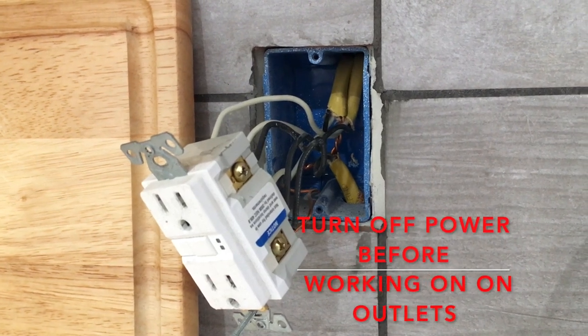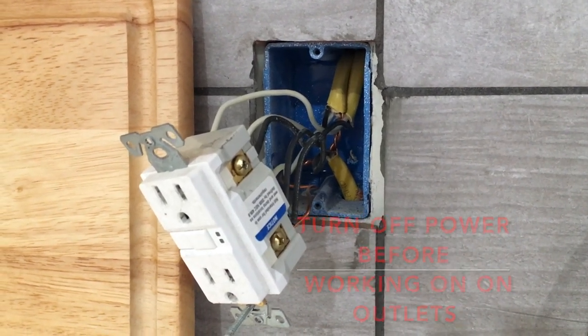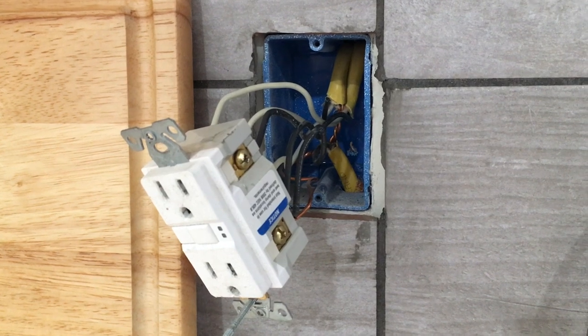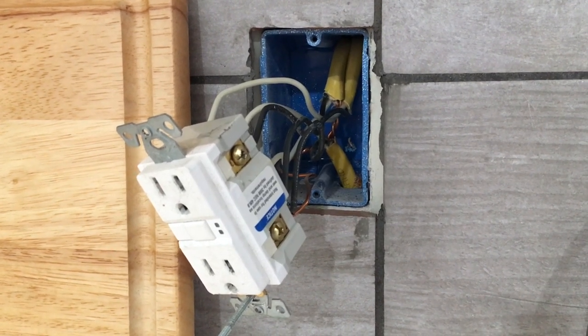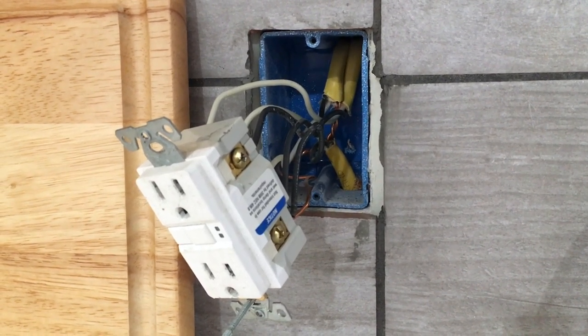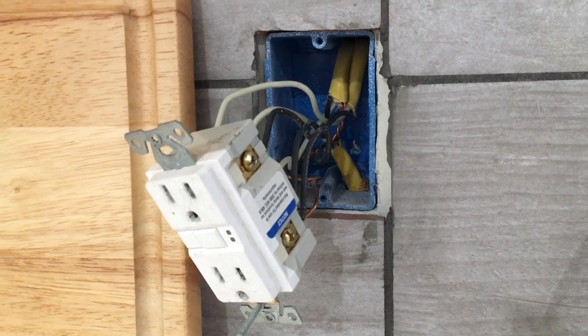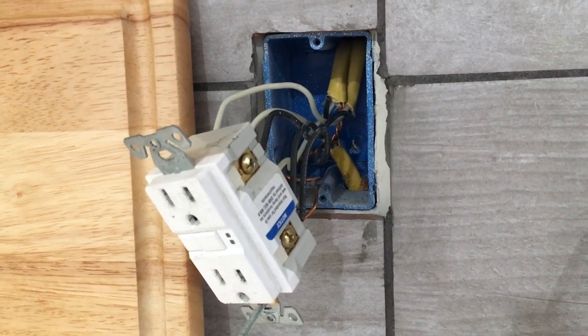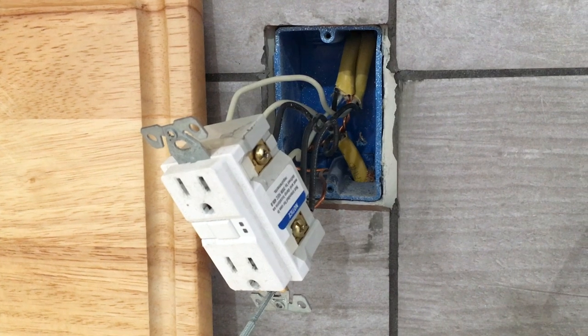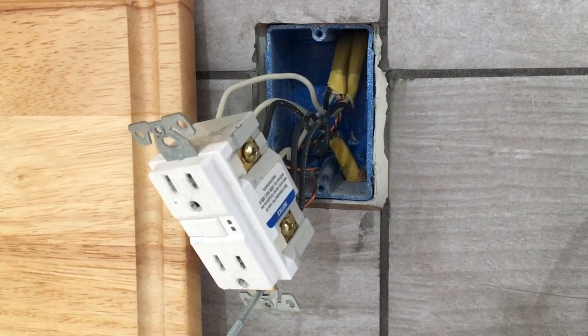This is a troubleshooting example. Here we replace a defective GFCI outlet that keeps tripping intermittently, but also we figure out which cables go where, how this outlet is powered, and what this outlet powers down the line—that is, other devices and electrical outlets.